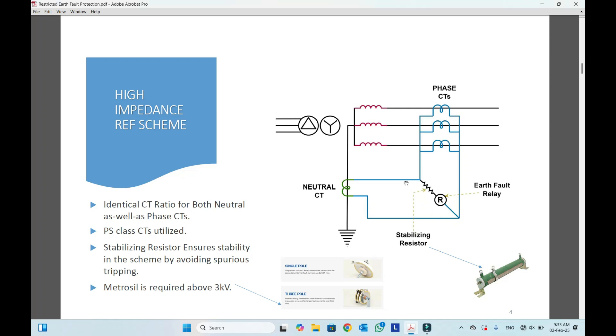The purpose of the metrosil is — the metrosil is a variable resistor, a voltage-variable resistor. If the voltage across it increases, its resistance will decrease and it will pass the current through that path instead of through this relay, because this is an external fault and we don't want an external fault to operate our REF. This is one kind of differential relay — the difference between the unbalanced current and the neutral current will flow through this relay.